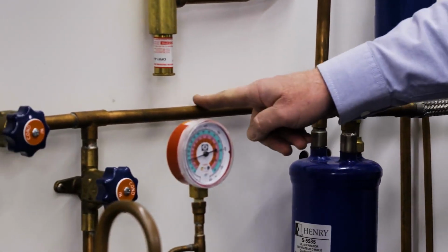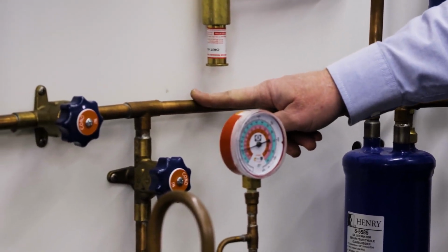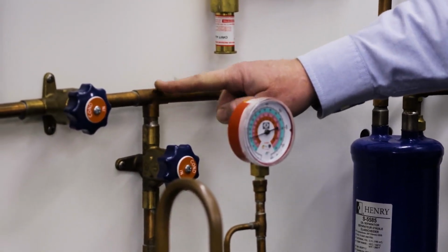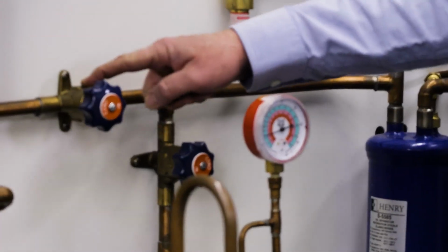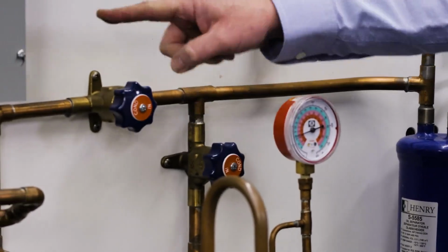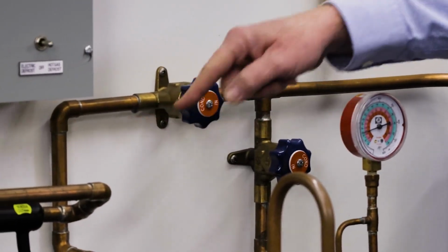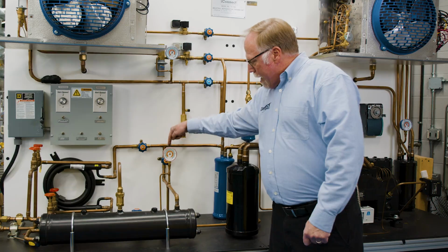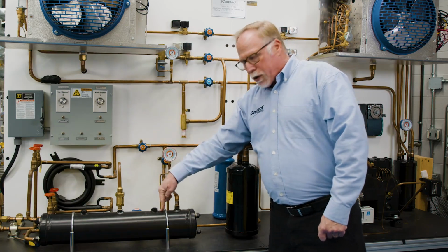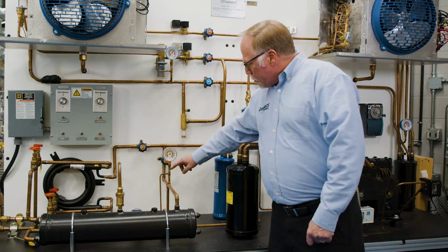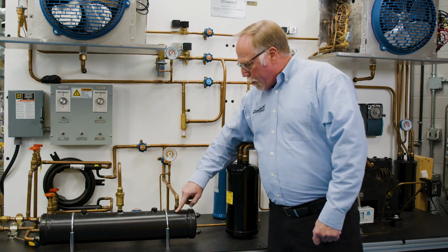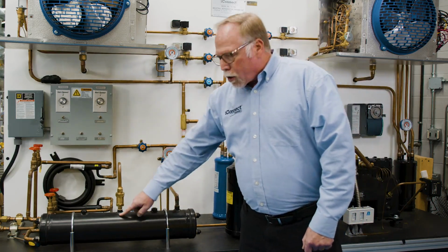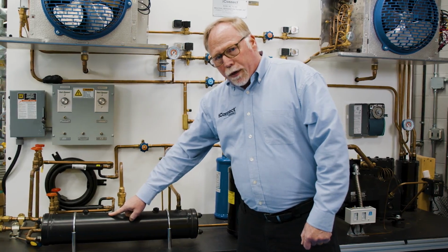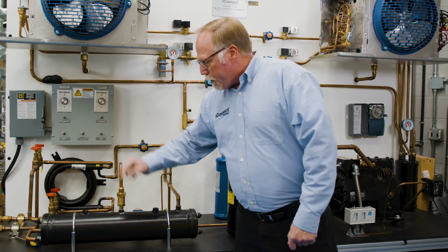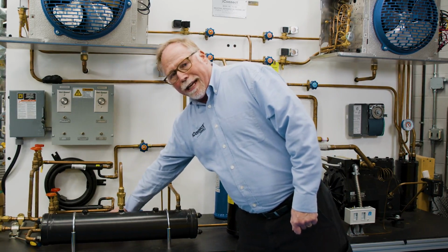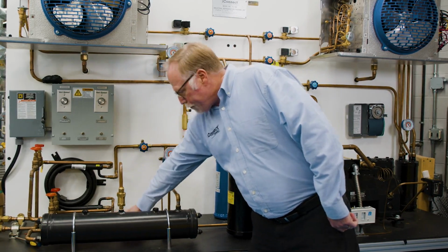So we're still coming out as a high pressure superheated gas. We're going to come down here. This valve here isolates the tube and shell condenser. I've got it closed. I've got it open to go to the tube and shell condenser here. So we go down through the tube and shell. We're going to reject the heat out of the refrigerant into the water. It's going to leave the tube and shell condenser as a subcooled refrigerant.